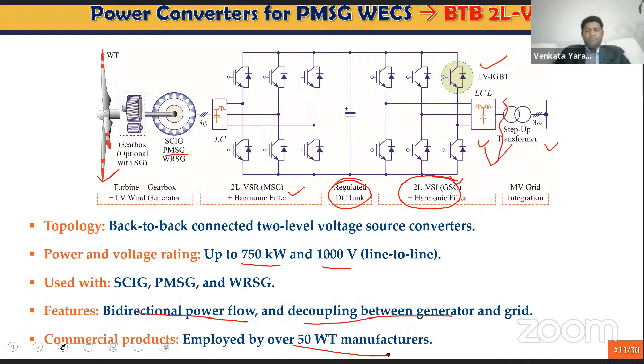This converter can be used up to 750 kilowatts. That is the capacity available in the market. There are some companies that now produce converters up to 800 or 850 kilowatts, and they can operate up to 1000 volts line-to-line. These converters offer bidirectional power flow and complete decoupling between the generator and grid. So if there is a fault on the grid side, the generator does not see that fault because it is isolated by the back-to-back connected converter. This is a very popular one, employed by over 50 wind turbine manufacturers.